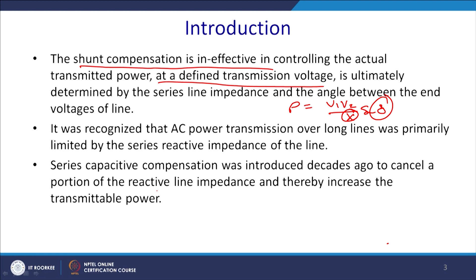It was recognized that AC power transmission over a long line is primarily limited by the series reactive impedance of the line. So ultimately it depends on X. If you can control X, then you can also control the flow of real power within the transmission system. As we discussed in our first or second lectures, series capacitor compensation was introduced a decade ago to cancel a portion of the reactive impedance and thereby increase the power handling capability of the power line, but it has some limitations.